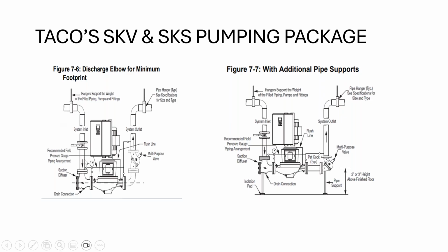And by the way, the Taco suction diffuser, please make sure you're familiar with these. It's a strainer. There's a strainer in there to pick up a last resort of big stuff before it goes into the pump. But the Taco suction diffuser has a startup strainer in it with a very fine mesh screen. After the system is started up, and I don't care if it's a vertical pump, an inline pump, or a base mounted pump, that startup strainer needs to be removed. It's in the instruction sheets. I say that enough, but just keep that in mind.